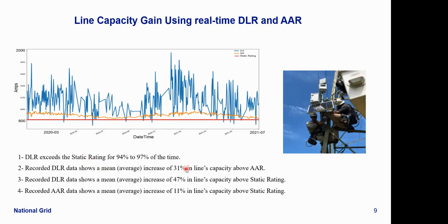So comparing DLR with static rating, I'm missing 47% in line capacity if I only rely on static rating for operations and planning. That 47% is just for one line we piloted this technology on, which is a big number. If I go with static rating, I have to keep upgrading the existing transmission line, adding to the cost of electricity delivery, whereas deploying DLR can help avoid that capital investment.